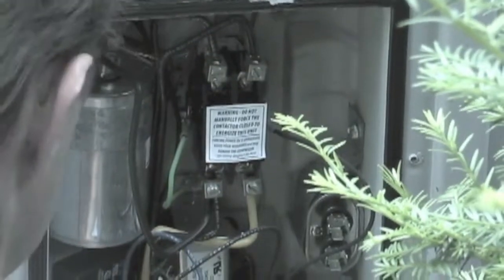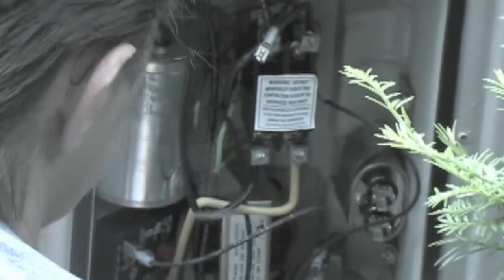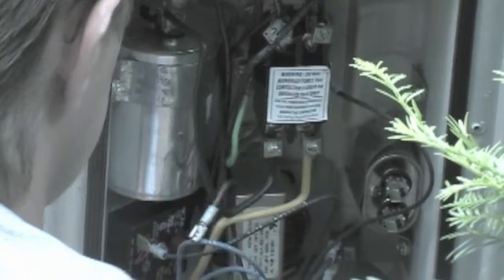Next, we are removing the compressor's wires. There are two heater wires at the top of the contactor on this model. Then you also remove the compressor wires from the bottom two lugs, black and yellow in this model. There is also a red wire connected to the run capacitor that you will be removing as well.